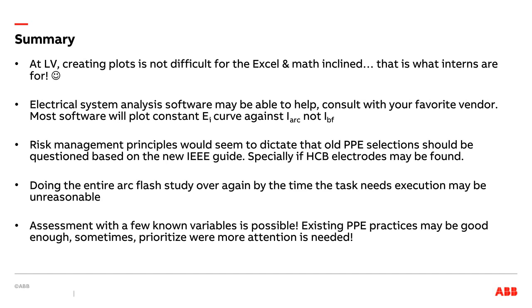If that's the case, just simply lower them by 1 or 2 calories. But it allows you to look at the task, being aware that if you have an HCB or VCB situation, you have a very different situation. Take that into account and decide whether your PPE is or is not good enough. Doing the entire arc flash study by the time the task needs execution may be unreasonable, but it is, at the end of the day, the best thing to do. So eventually, you should do that.